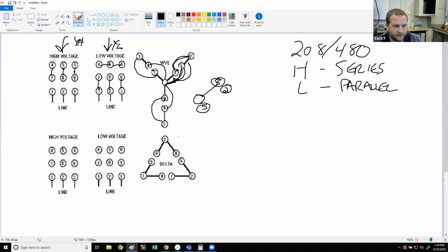All right, let's look at delta high. So we're going to do this. What are we doing? It's delta high, so series or parallel? High voltage, series. Same kind of thing. 6 goes to 9, 5 to 8, 4 to 7.